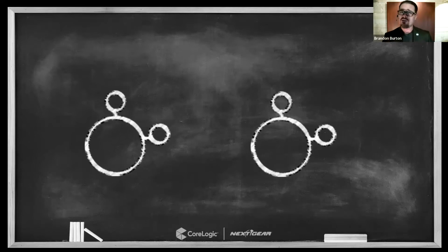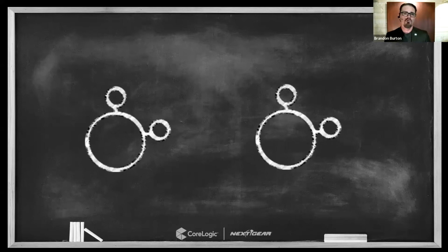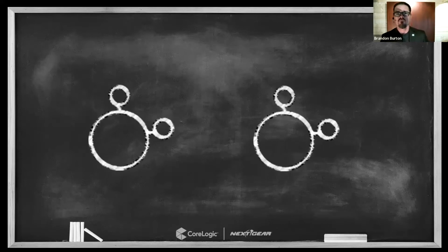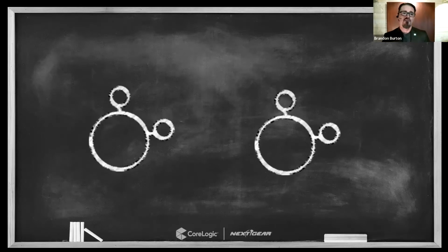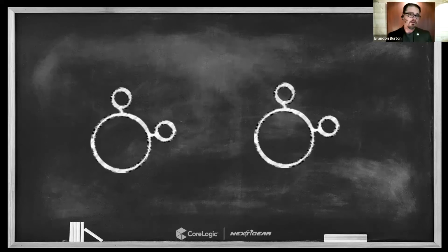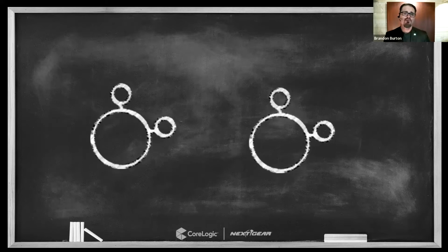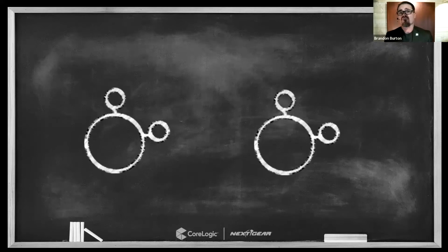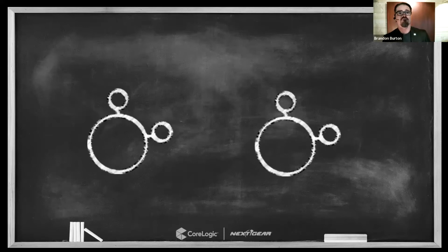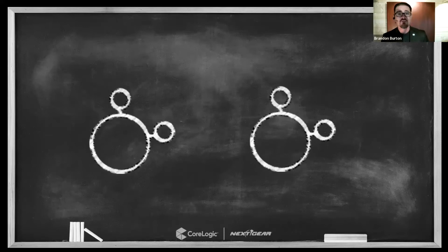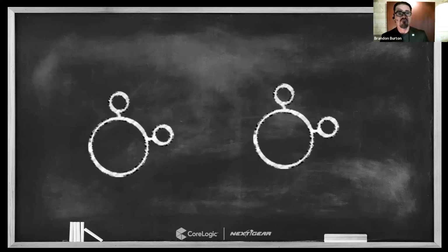We've discussed it a little bit in some previous Technically Speaking episodes. We've kind of broached the surface. Today, we're going to go a little bit deeper and better understand why dew point is such an important tool. To the extent that I would actually make the claim that if we understood dew point well enough, you wouldn't even need grains per pound, right? Grains per pound is a measurement we've historically and traditionally used in this industry, but believe it or not, you could replace grains per pound with just dew point and consider all of your drying documentation in just dew point, and walk away with a much better understanding of what's happening than grains per pound.